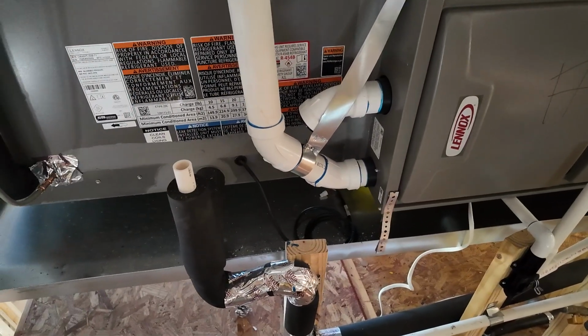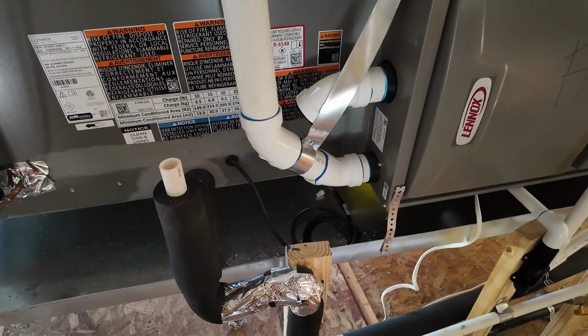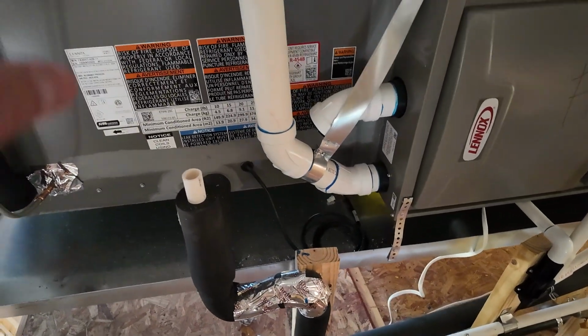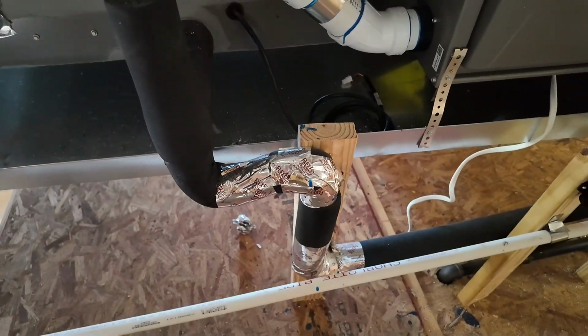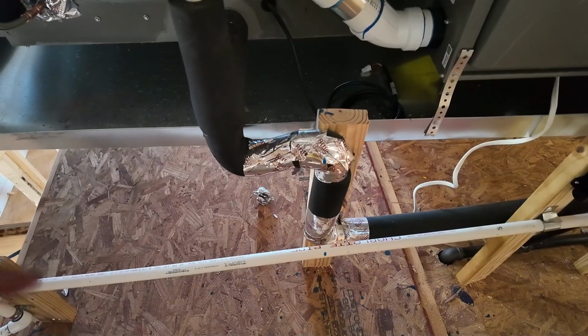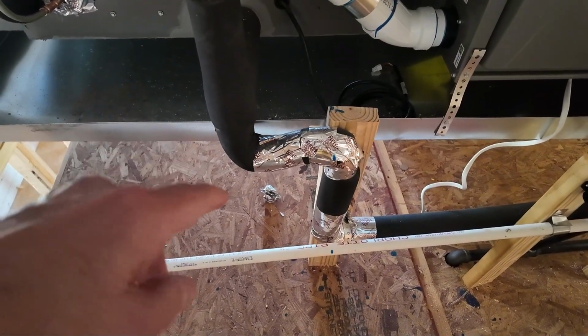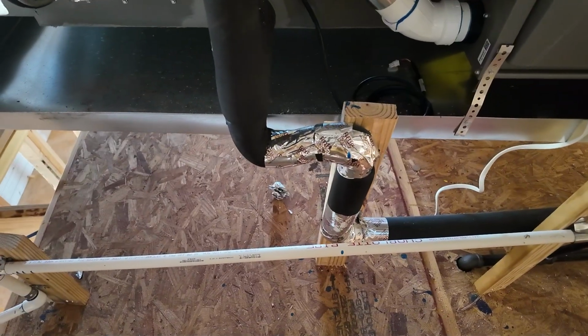And then when the fan turns off, the thermostat's been satisfied. What happens then? All the water drops at once. Water drops at once, comes down here, we have a shallow trap. It's just like a yogurt commercial. Swoosh! Or it's a roller coaster. Last car follows the first, comes in. This is not a self-cleaning trap, but it is a self-clearing trap.